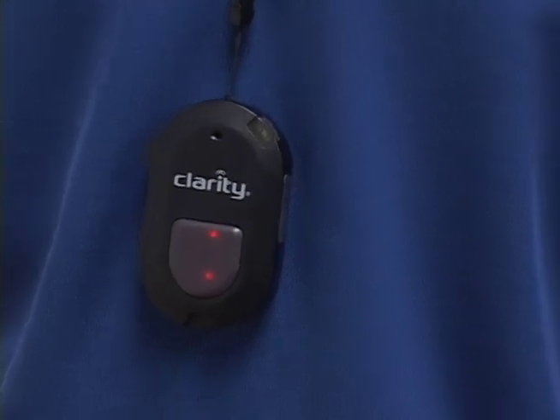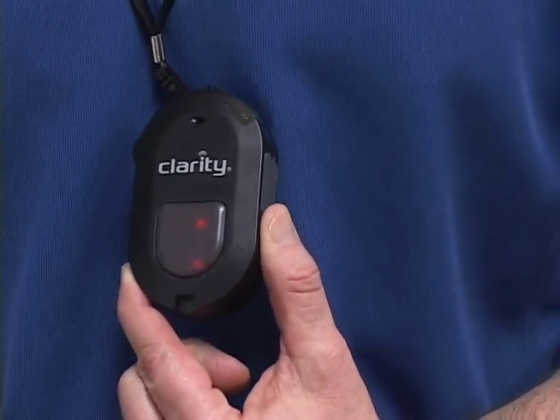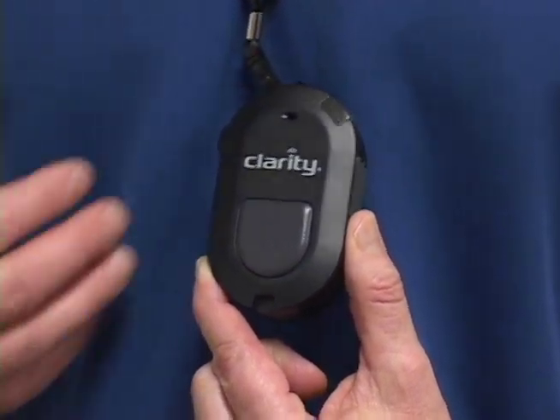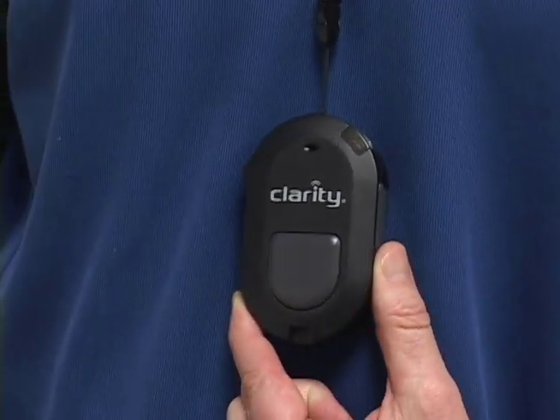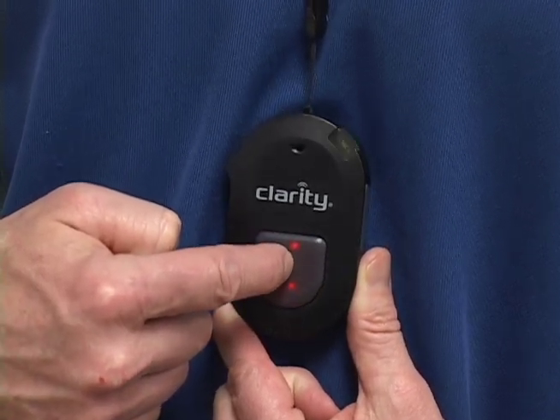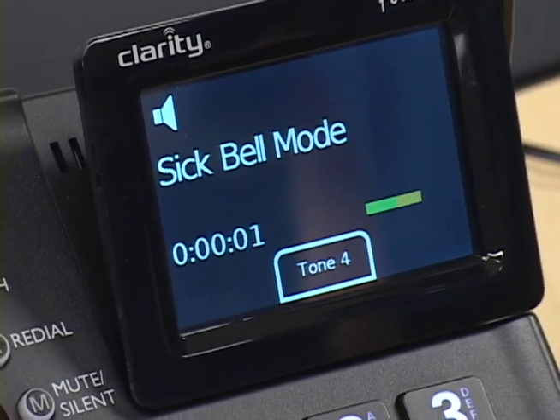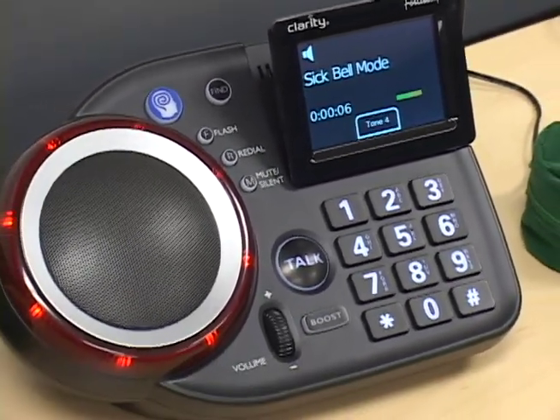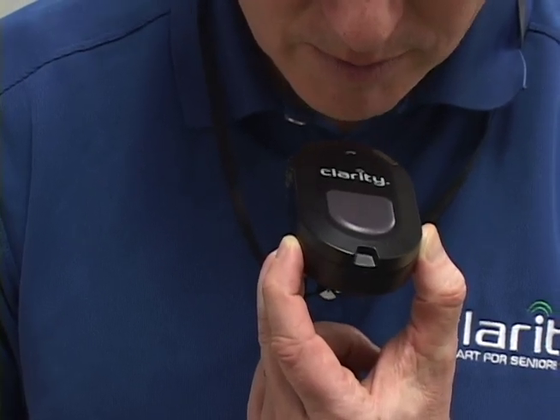Sick Bell is an option within the Fortissimo that allows the pendant to be used to transmit a message to the Fortissimo so that it then broadcasts like an intercom. That way, the person wearing the pendant can call for assistance if needed. After the feature is programmed into the Fortissimo, you simply press and hold the pendant button for three seconds, then release.